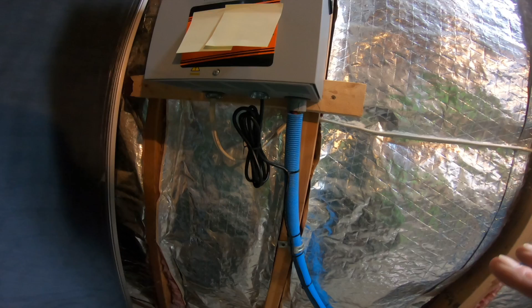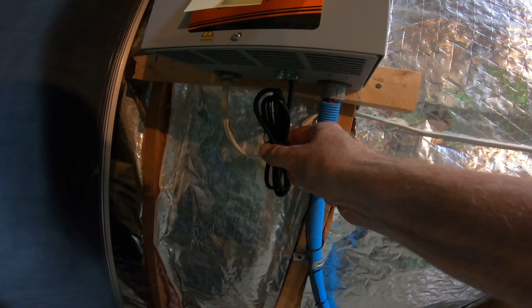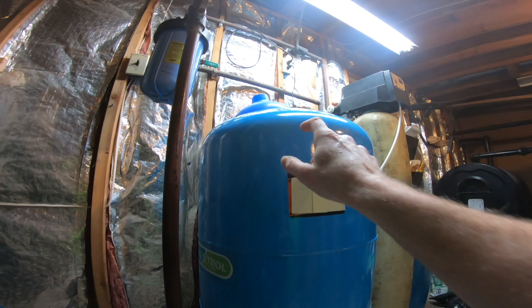Okay, here's the electric, and it's zip tied to a transducer wire. Not only shouldn't it be zip tied, but where this crosses, it's got to be at 90 degrees. So this is parallel the entire way down. That's wrong. Third thing, the company put out a video, and they said when installing this, the extra transducer wire, here it is, do not bunch it together and zip tie it under here, or it's going to interfere. Cut off the extra.